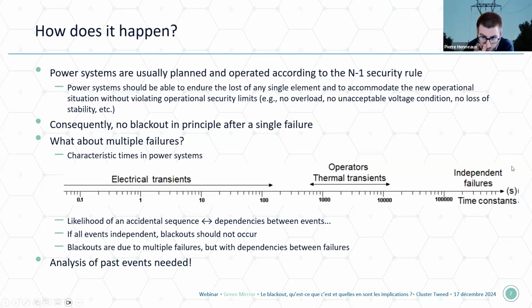And then you can obviously have independent failures. You can have two elements in your grid that fail for independent reasons. But typically the failure rate of elements is of the order of magnitude of once per year, sometimes lower for transmission elements, sometimes a little bit higher for generating units. That's typically the kind of thing you can have. And so if you have once per year, it means that with 100 independent elements, you will need to wait some time to have two independent failures arriving. And because you need to wait, in the meantime, operators can take corrective actions.